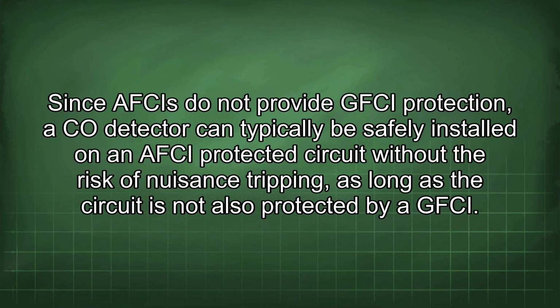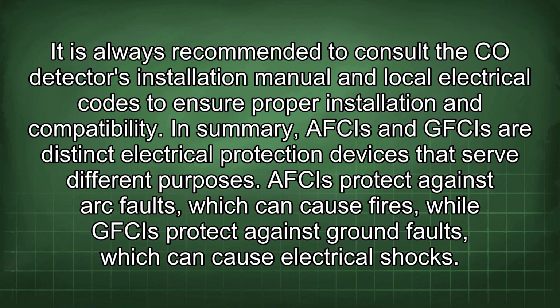Since AFCIs do not provide GFCI protection, a CO detector can typically be safely installed on an AFCI-protected circuit without the risk of nuisance tripping, as long as the circuit is not also protected by a GFCI. It is always recommended to consult the CO detector's installation manual and local electrical codes to ensure proper installation and compatibility. In summary, AFCIs and GFCIs are distinct electrical protection devices that serve different purposes.